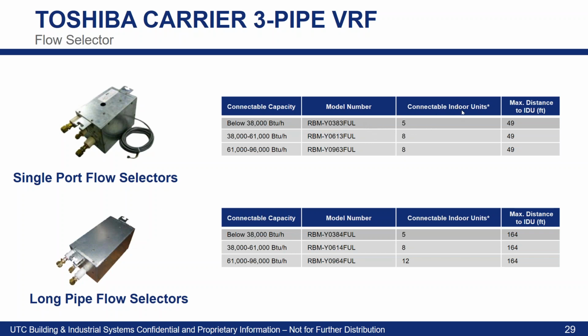And this here shows how many indoor units we can actually connect to our single port boxes. You see our BTU ranges here, 5, 8, and 8. Honestly, guys, we'll never see this. I've connected maybe 2, 3 max to a single port box. It just doesn't lay out right when you're having multiple indoor units hanging off of this. I've never really seen it. It doesn't make sense really, but it is available for that oddball application.